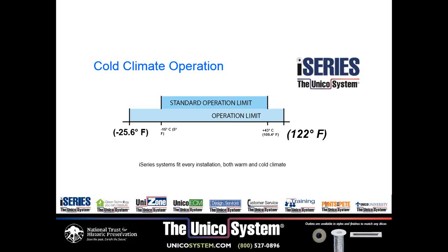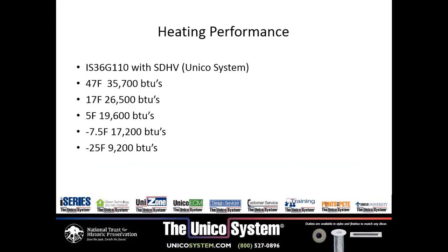Here you can see our operation limit. We're very comfortable in running these down to 5 degrees above zero. Even at 25 below zero, this system is still producing more energy than it's using. These are the numbers for our 3-ton system: at 47 degrees, you get 35,700 BTUs. At 17 degrees, which is the other number that we're required to test at, we get 26,500 BTUs. At 5 degrees, which for most parts of the United States is our design temperature, it's putting out almost 20,000 BTUs. Now, if it is 25 degrees below zero, the system is still producing heat, but about 9,200 BTUs.